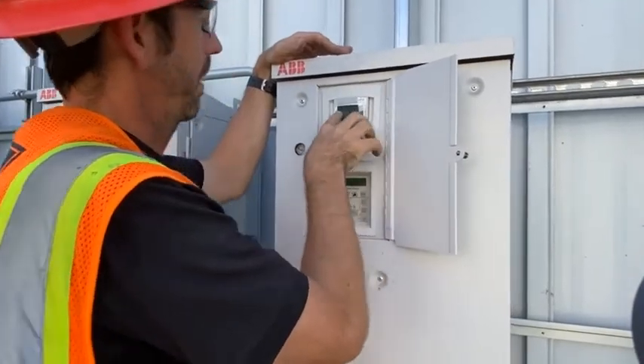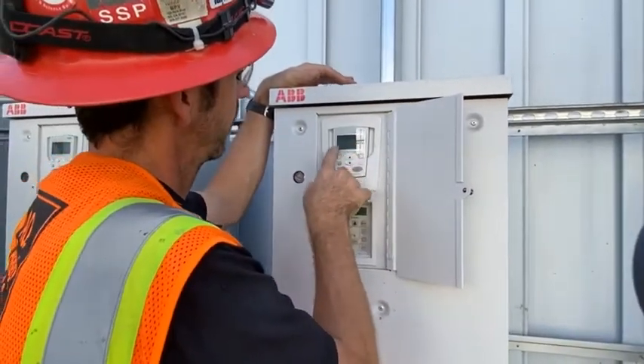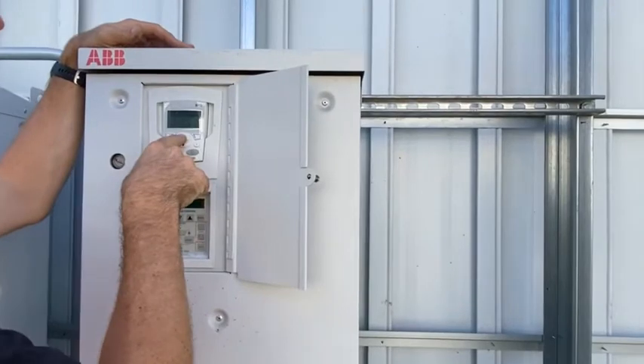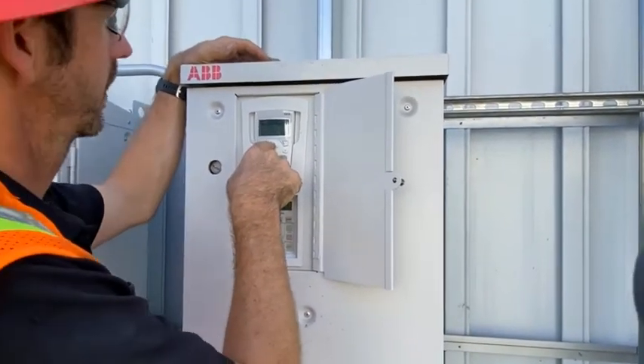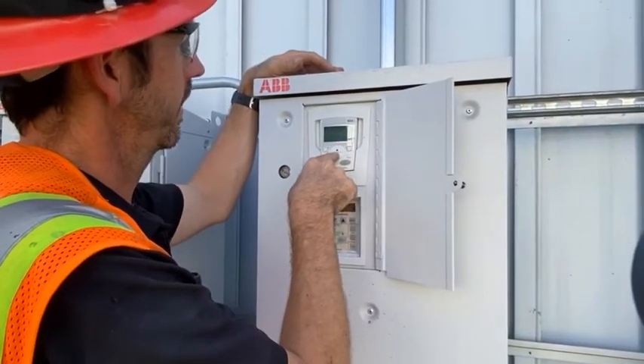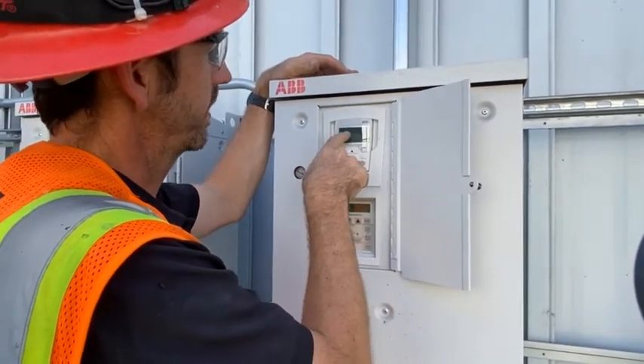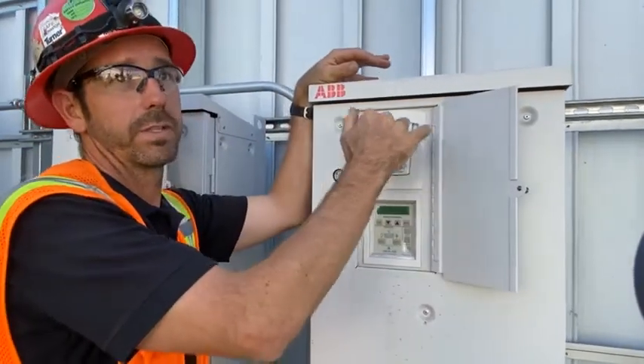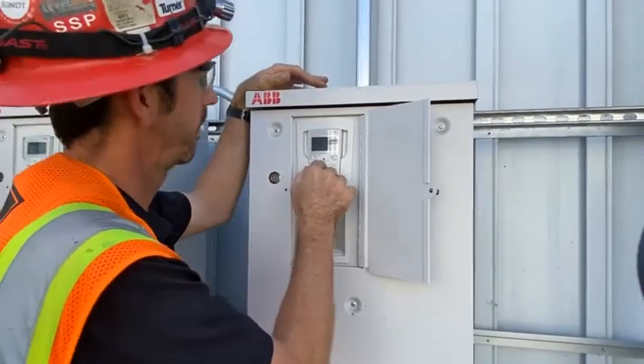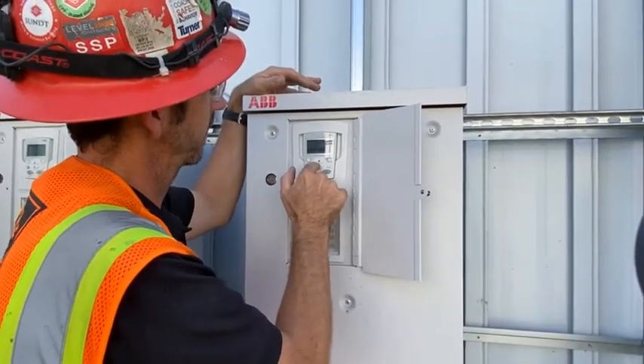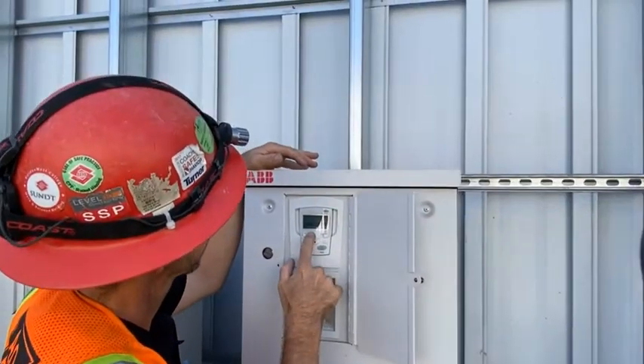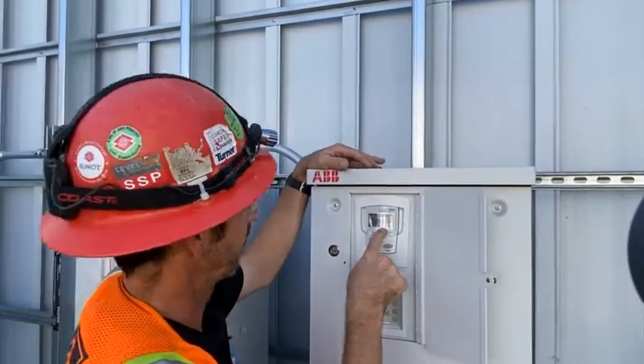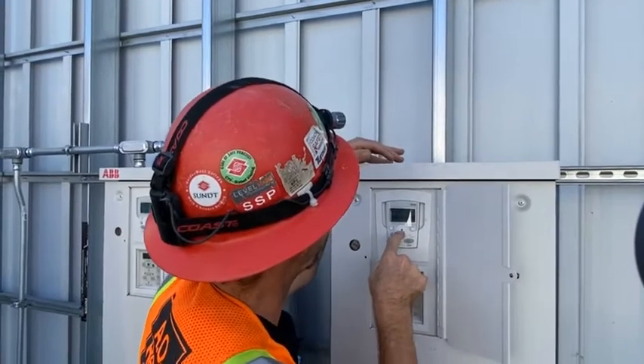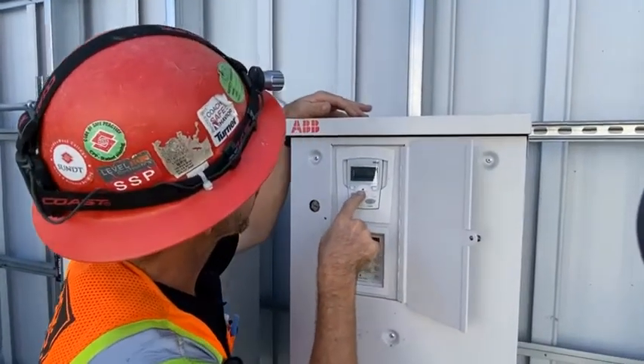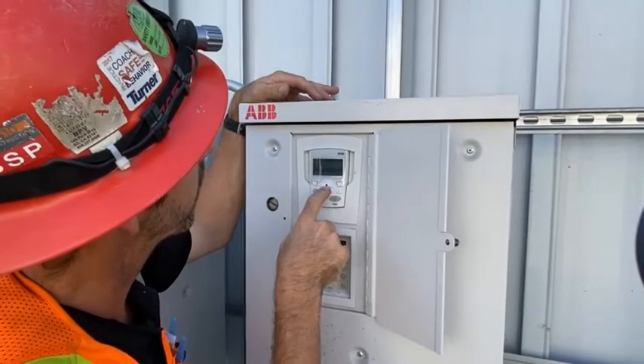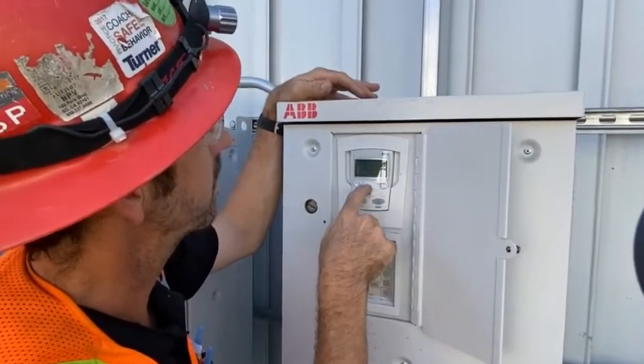So what we do is we go into parameters. I press menu. We go up to 34. 34 is panel display. We select it. We got signal 1. So we don't want 1. 1's on the top, 2's on the bottom, and 3 will be the bottom one. So we go all the way down to signal 3. It's still an analog input signal coming from the drive. We go down to display form. It needs to be on direct.